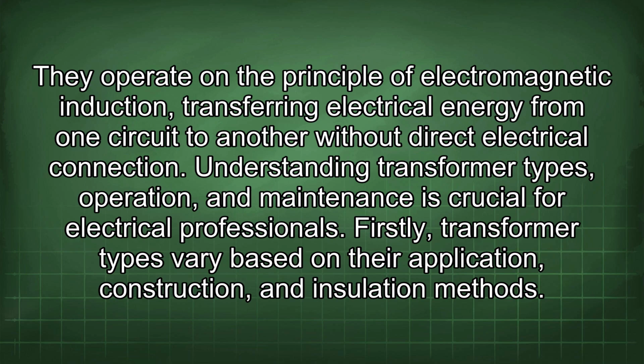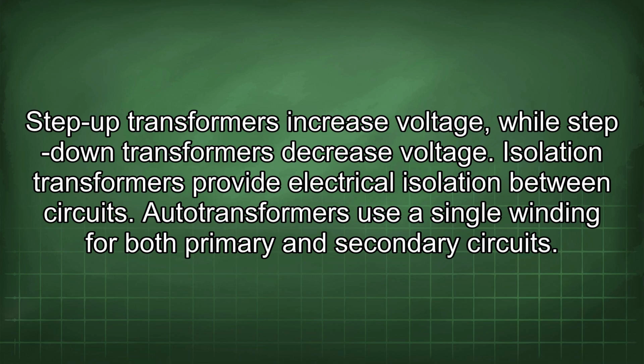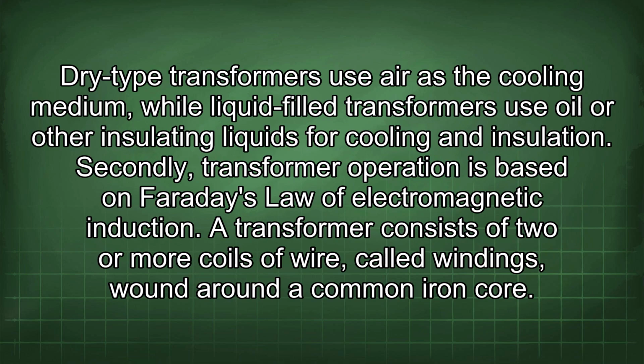Firstly, transformer types vary based on their application, construction, and insulation methods. Step-up transformers increase voltage, while step-down transformers decrease voltage. Isolation transformers provide electrical isolation between circuits. Autotransformers use a single winding for both primary and secondary circuits. Dry-type transformers use air as the cooling medium, while liquid-filled transformers use oil or other insulating liquids for cooling and insulation.